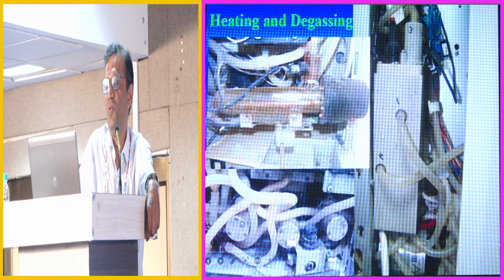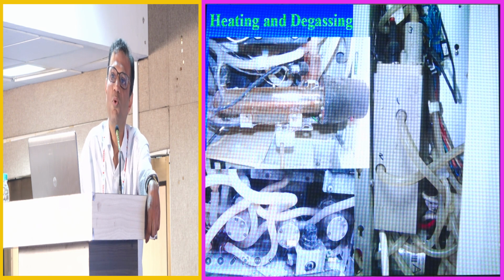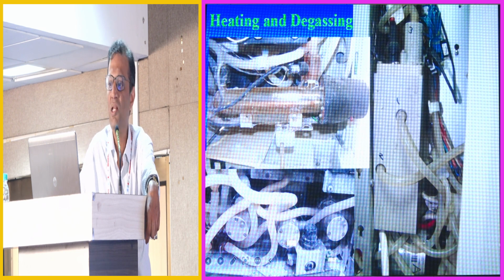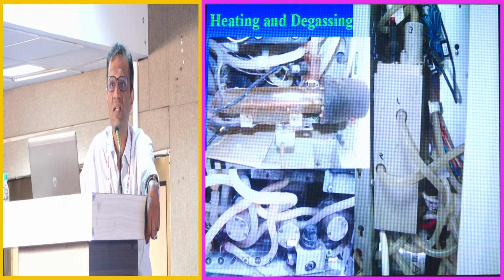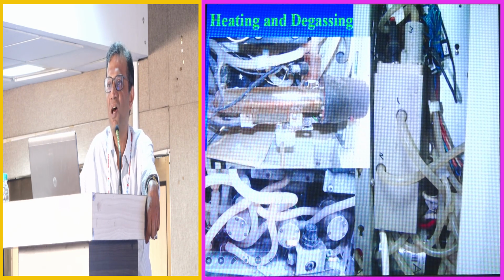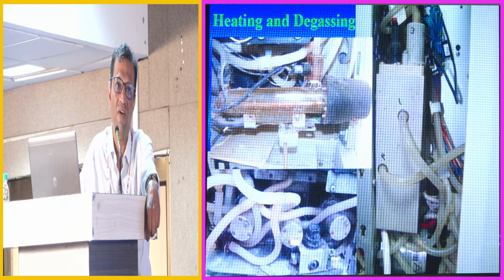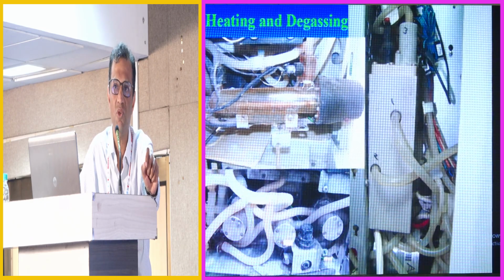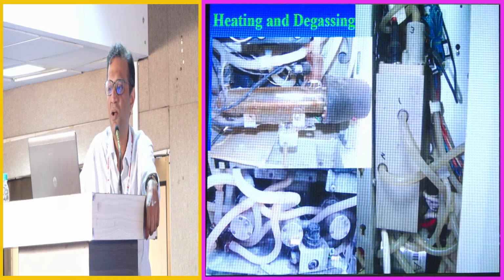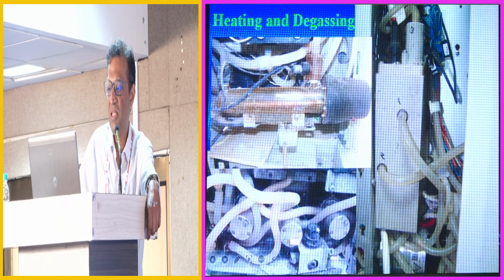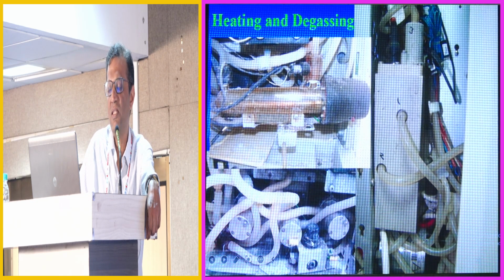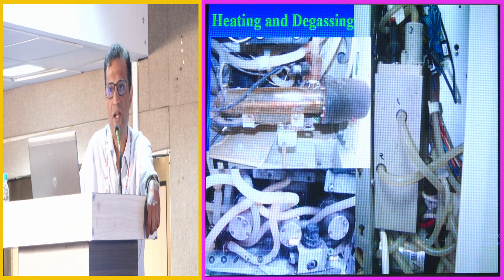Okay, so the machine must heat up the incoming water, which it does with the help of this heater. This heater is what consumes most of the power in a dialysis machine. It's 1500 watts, which means it takes about 7 amps of current. And so if you place a 5 amp plug to your dialysis machine, it's going to throw your circuit breaker or blow the fuse.